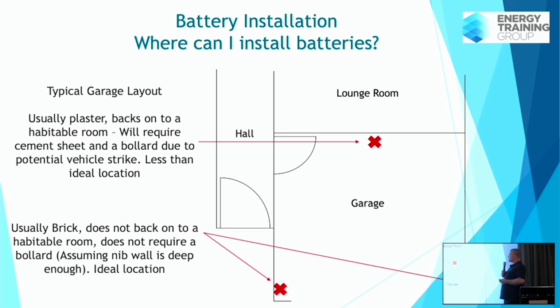So in a garage, I found that the best place to install our batteries was in these front 2 corners just here, right? In a garage, you'll usually find that this wall's plaster, and they back onto a habitable room, okay? So you need to fireproof the wall when you're backing onto a habitable room. Any habitable room is like lounge room, study. Think of it as anywhere where you could have a couch or a bed. That's a habitable room. So you really want to put your batteries so they're not backing onto a habitable room. Obviously, the external wall of the garage is not a bad idea because you don't have your fireproofing requirements.